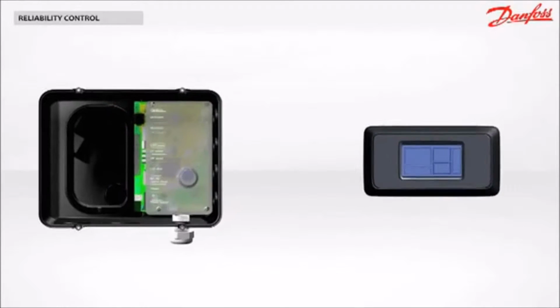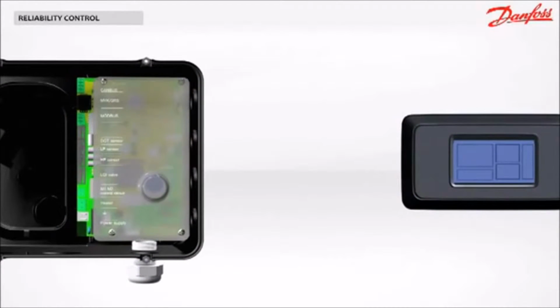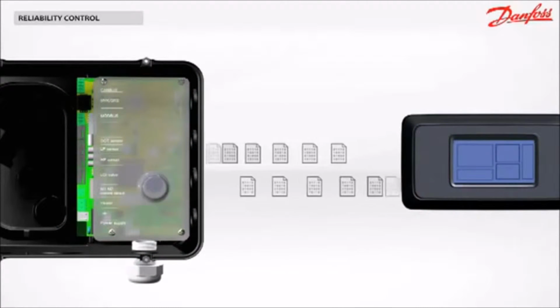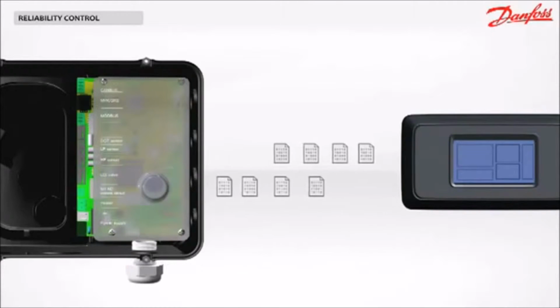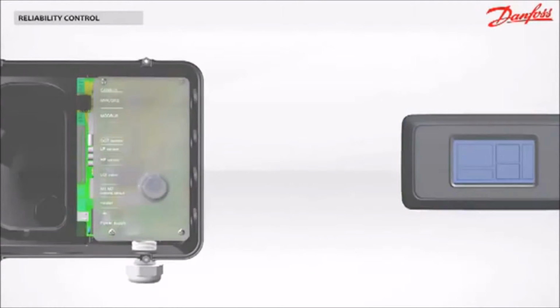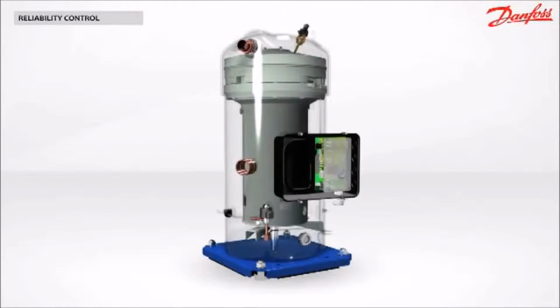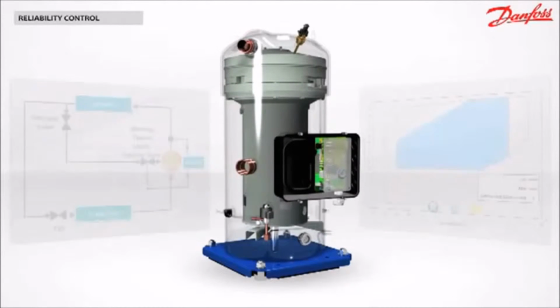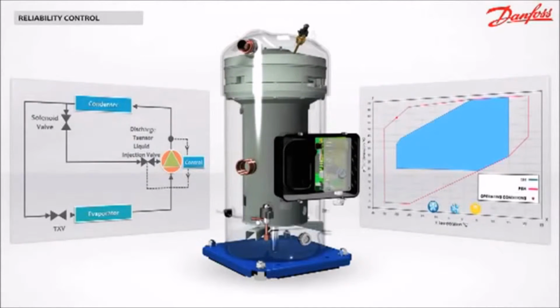The OCS module is able to communicate operating parameters, warnings and alarms through Modbus with the system control. When the compressor runs for too long outside the operating map, the module shuts down the compressor.